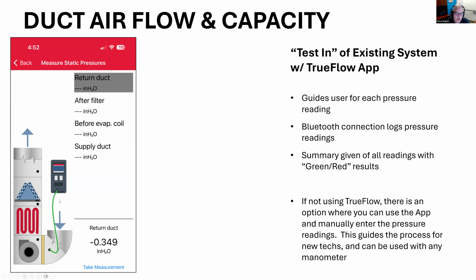And then you can see there's 4 spots here with the manometer shown connected to the return duct before the furnace filter. And this image will change depending on which type of system you choose. And it will guide the user through making a static pressure measurement with the system in normal operating conditions. You want to get it ramped up to 100%. And with the regular furnace filter in, so just normal operating conditions, we're just going to measure the pressure in 2, 3, or 4 locations to map the static pressure. Then after that, they will put the grid in place of the filter, and make another measurement of airflow and a second static pressure measurement.